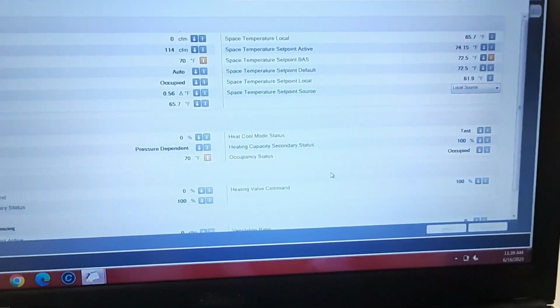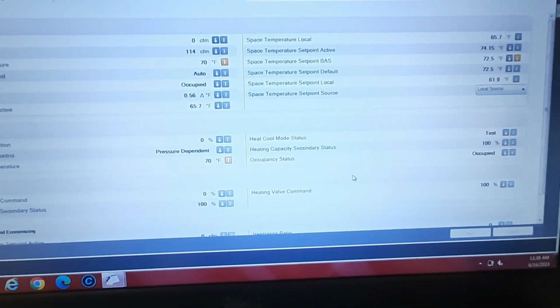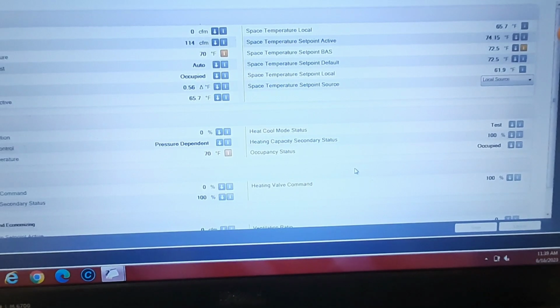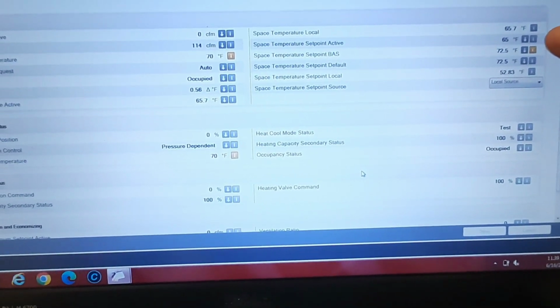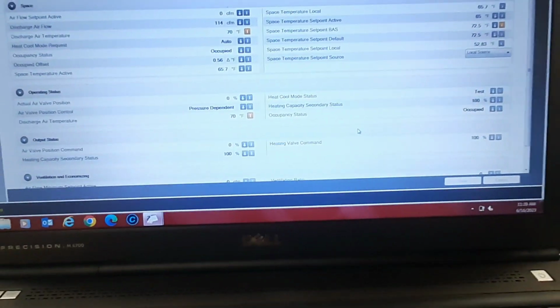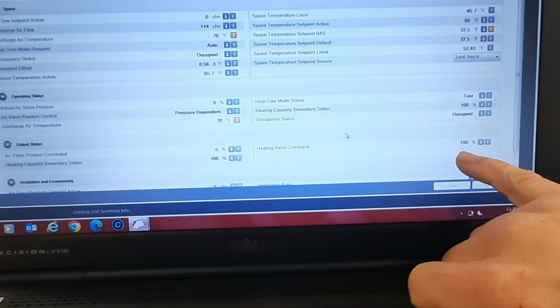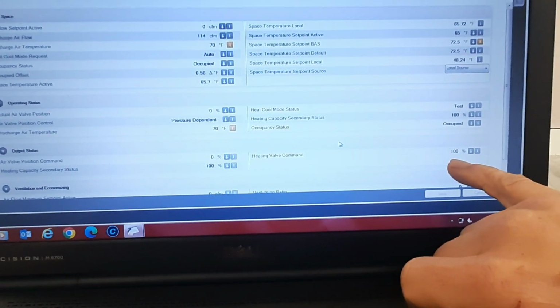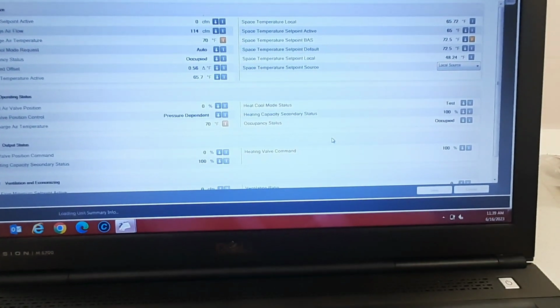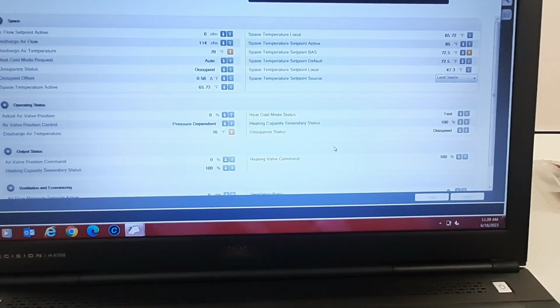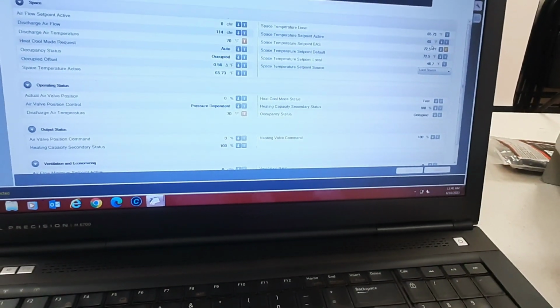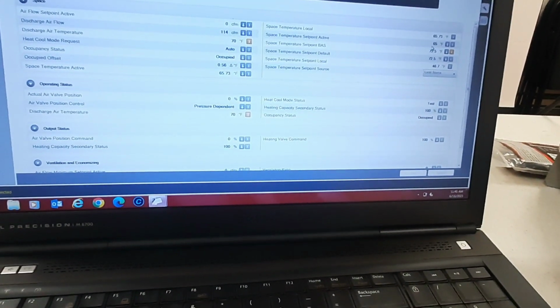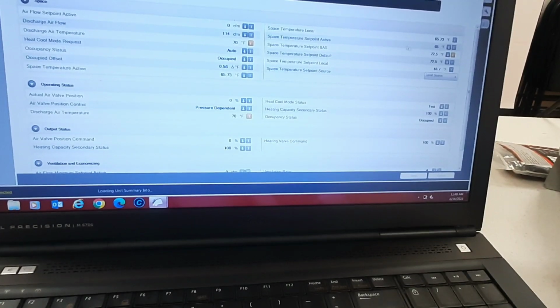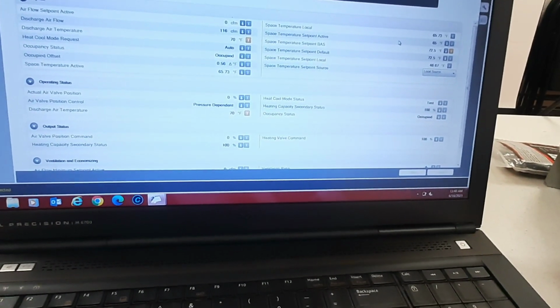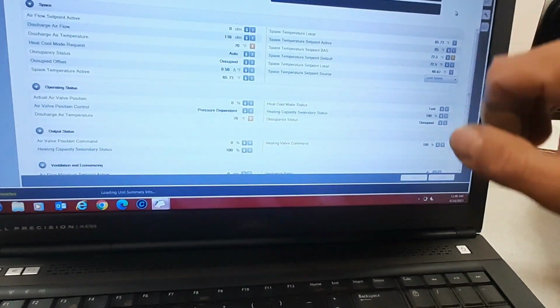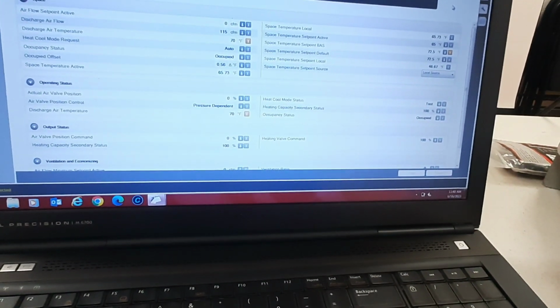Everything seems like it's gonna work. There goes my set point local down. Set point active is gonna go to the minimum, which is 65. My heating valve command should go to 0. Should. Again, I don't know why it still shows me in test. For now, I'm gonna go ahead and lower my low limit set point, and see if I can't get that valve to drive open, because it's 65 degrees in here.